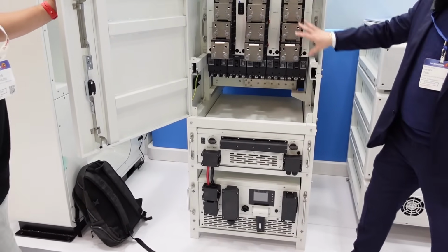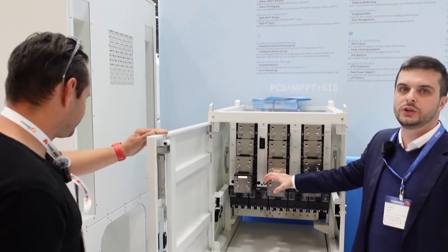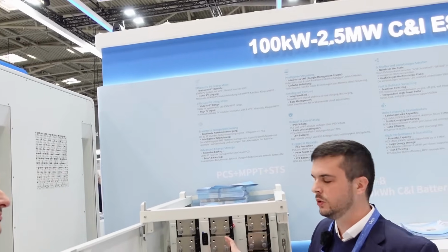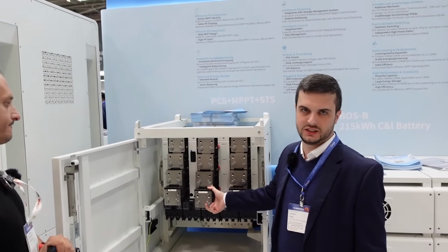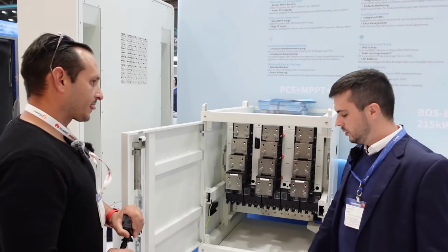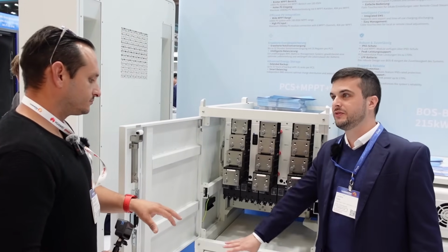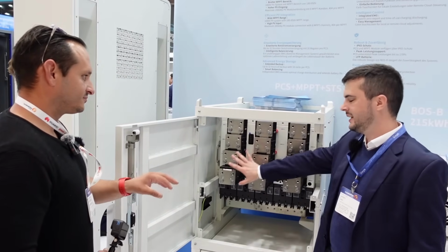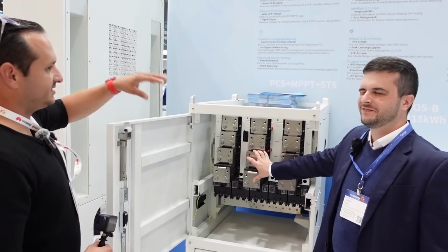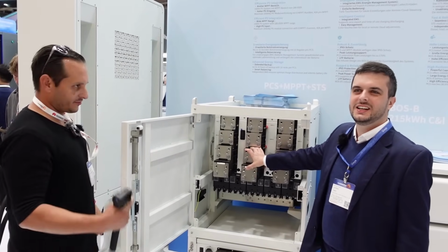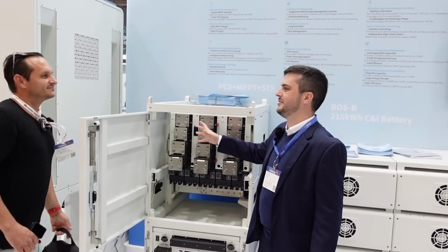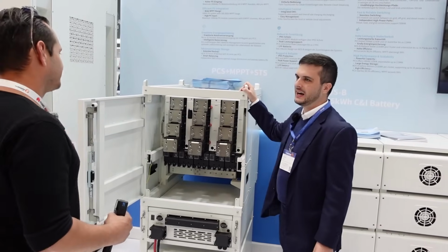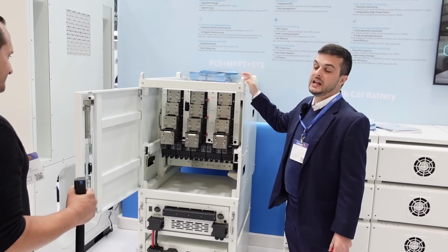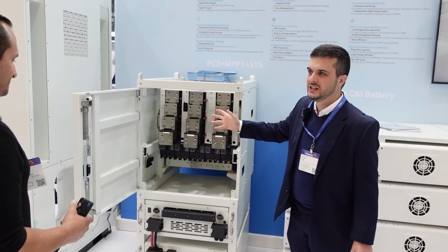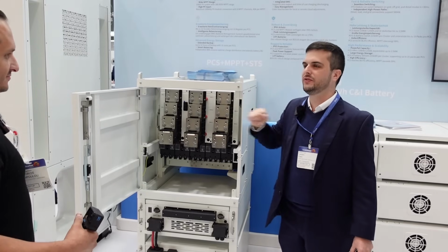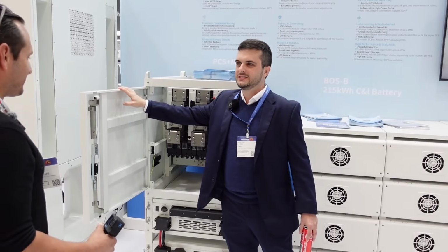You don't need to use this part for each inverter. You can parallel 5 inverters and 5 MPPTs per STS. So the STS is for up to 5 units, meaning you only need to buy one and use it across 5 inverters.